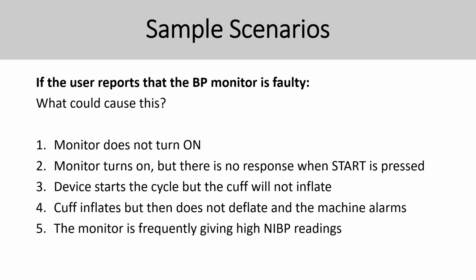Okay. So number 4 is correct. When there's some sort of leaking in your cuff, the cuff tries to keep on pumping and pumping. Eventually, it cannot give you a reading, and it starts to give an error code with the machine alarm. Number 5 is cuff sizing. So your size is wrong, and you end up getting a high reading. Sometimes your body movement will give you a high reading or a low reading. It depends on the cuffs also. So most of you got it right. These are scenarios that you're going to see with the user.